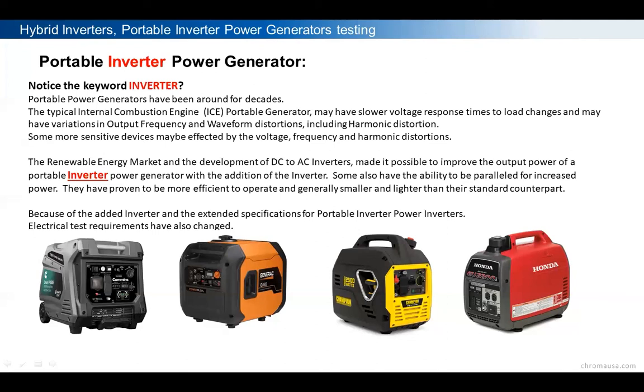There are a number of good units on the market. But the difference with this one is that a standard power generator gets its output directly from what we call an alternator. The alternator output voltage is regulated by regulating the RPM of the motor, through a feedback loop that controls the throttle and gas to the engine, and it's a very slow response. So regulation of your output under varying loads can vary greatly on a standard generator. It can also vary the frequency, since frequency is determined by the pulley system between the alternator and the engine, and the RPM of the engine.